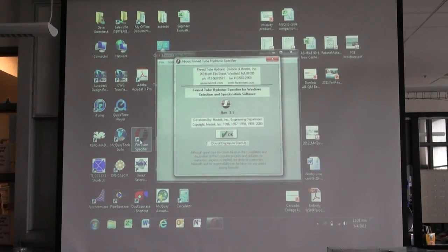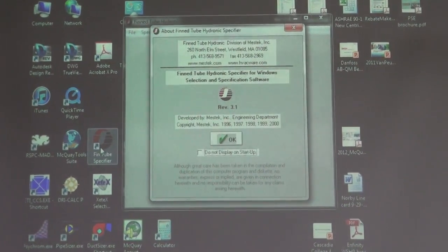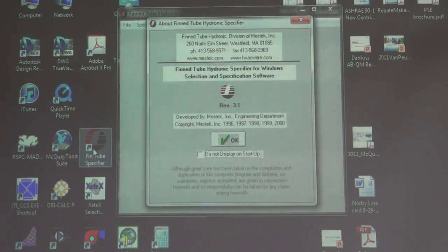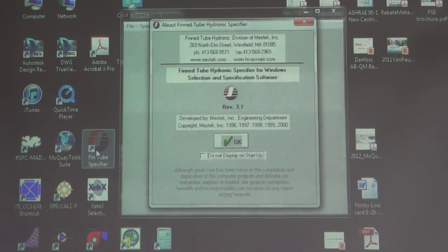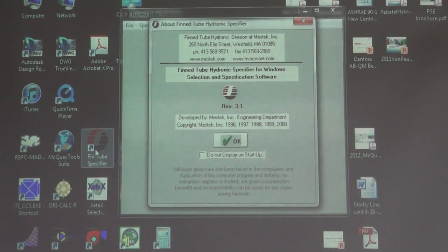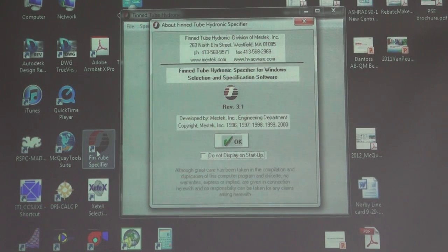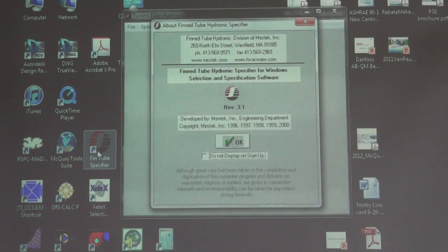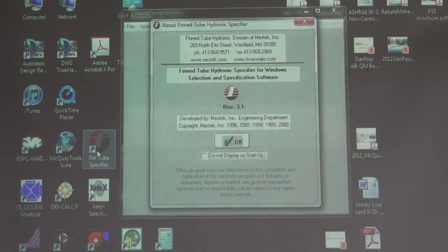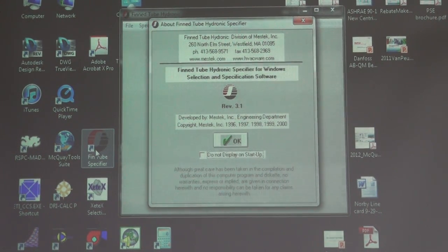Okay, so fin tube is really simple. And nobody in the industry spends any time on it, so it always gets screwed up. We figured that out about 12 years ago, just when I came to Norby, and decided I was going to handle all of it. I do probably about a third of the industry's designs, and half of those are usually custom stuff. That's what fin-tube manufacturers are really good at, just bending metal. It's just a sophisticated sheet metal shop. And having some empirical data, because they're not going to test every one of these applications. For example, when you've got two tiers high, the second tier will do maybe 40% of the first tier.